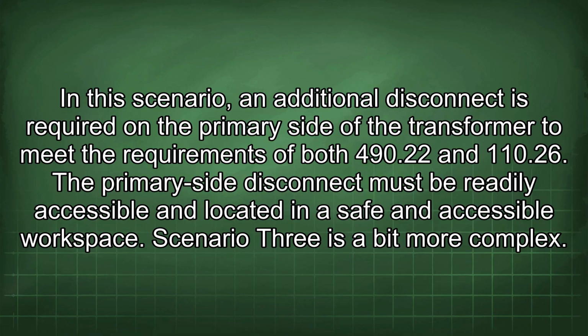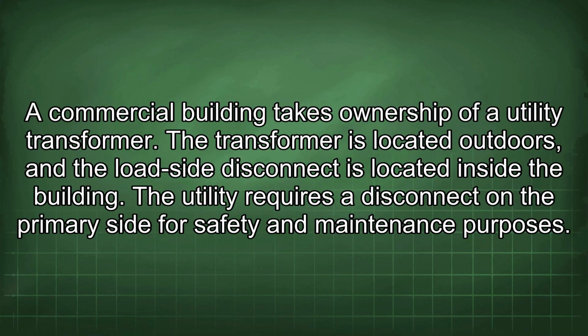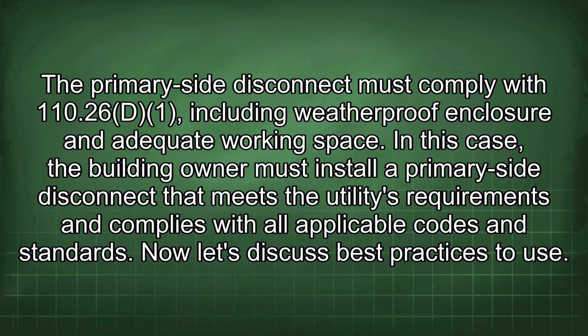Scenario 3 is a bit more complex. A commercial building takes ownership of a utility transformer. The transformer is located outdoors, and the load side disconnect is located inside the building. The utility requires a disconnect on the primary side for safety and maintenance purposes. The primary side disconnect must comply with 110.26, including weatherproof enclosure and adequate working space. In this case, the building owner must install a primary side disconnect that meets the utility's requirements and complies with all applicable codes and standards.